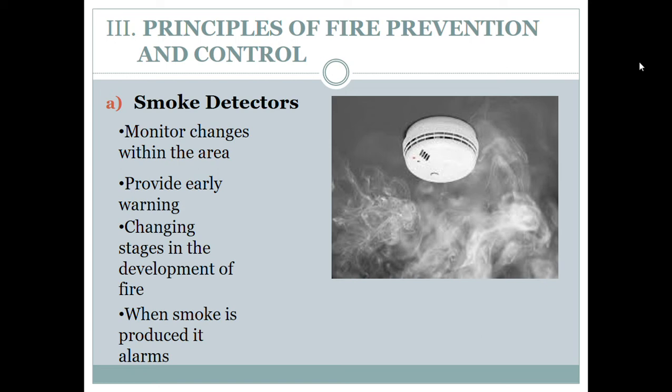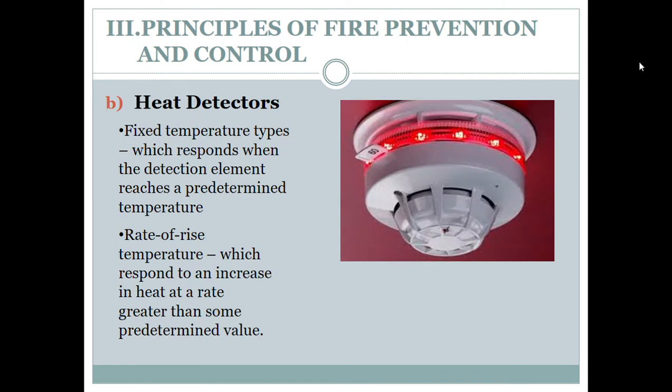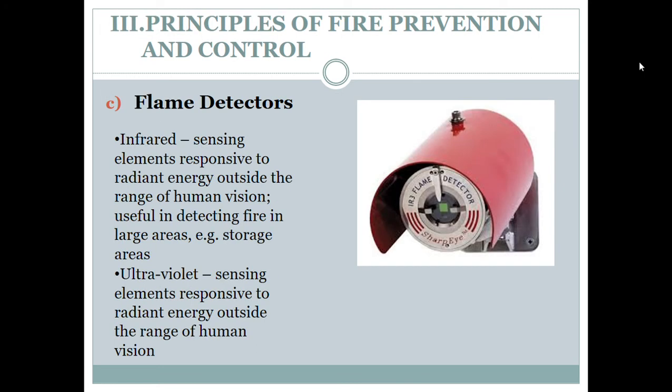Smoke detectors monitor changes within the area and provide early warning at changing stages in the development of fire — when smoke is produced, they alarm. Heat detectors have two types: fixed temperature types, which respond when the detection element reaches a determined temperature, and rate-of-rise types, which respond to an increase in heat at a rate greater than some predetermined value. Flame detectors include infrared and ultraviolet types; both sense elements responsive to radiant energy outside the range of human vision and are useful in detecting fire in large areas such as storage areas.